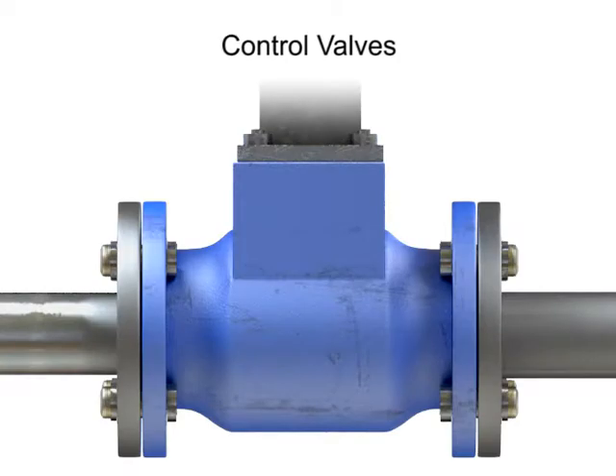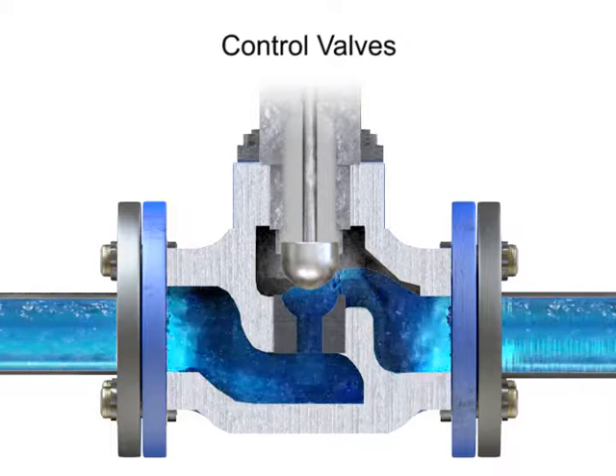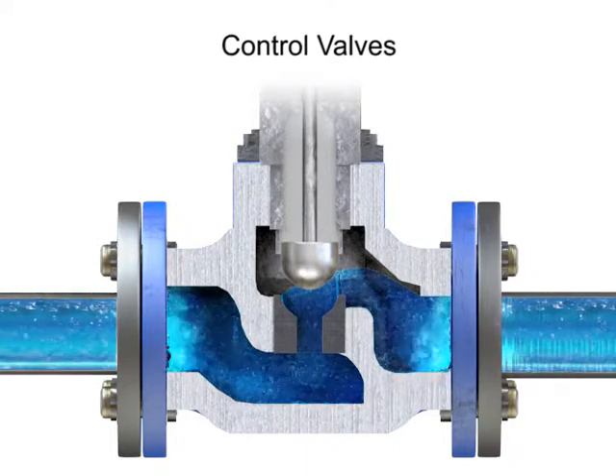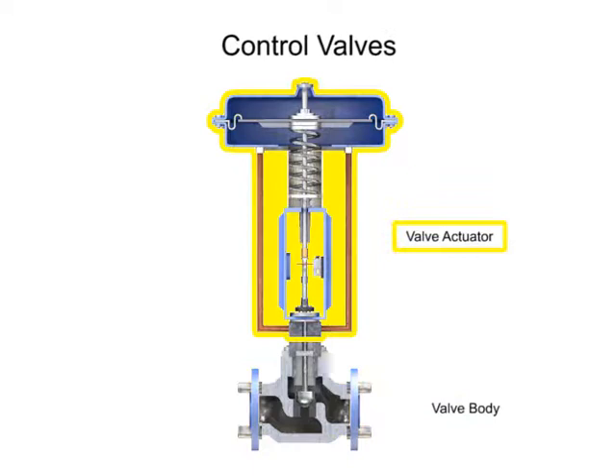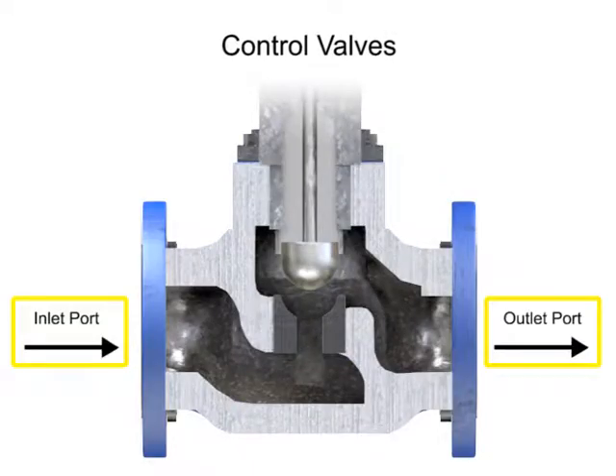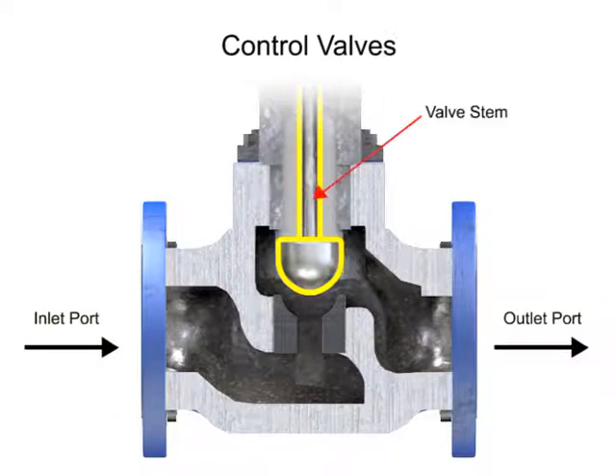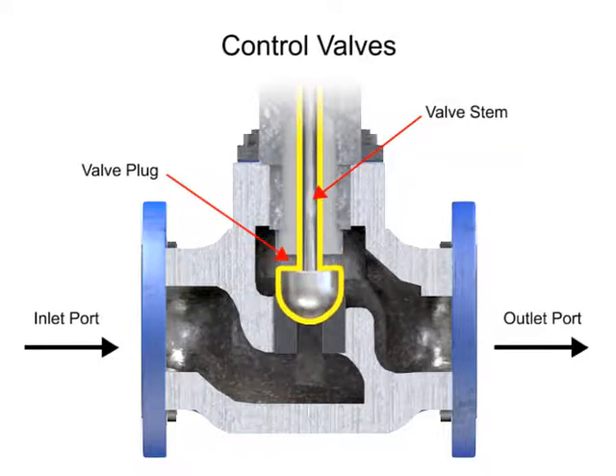Control valve actuators control fluid in a pipe by varying the orifice size through which the fluid flows. Control valves contain two major components: the valve body and the valve actuator. The valve body provides the fluid connections and a movable restrictor, comprised of a valve stem and plug that is in contact with the fluid that varies the flow. The valve actuator is the component that physically moves the restrictor to vary the fluid flow.